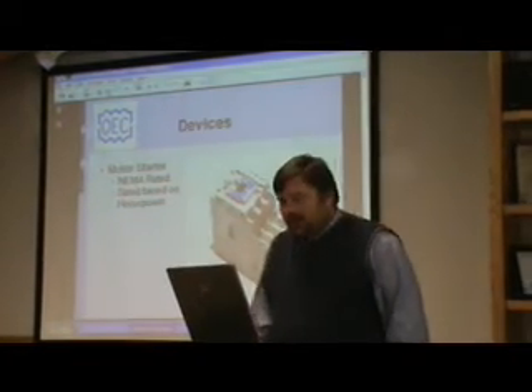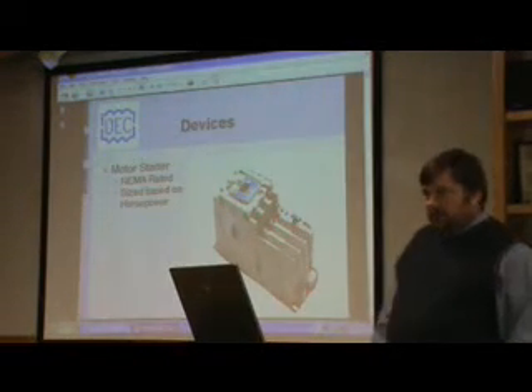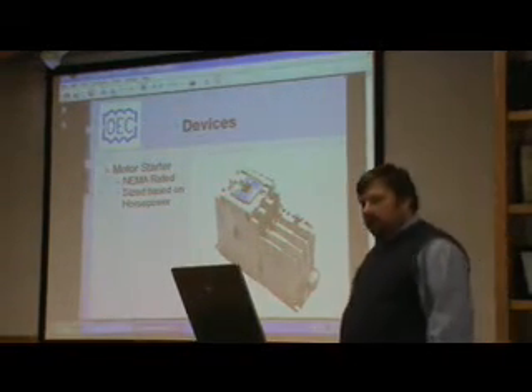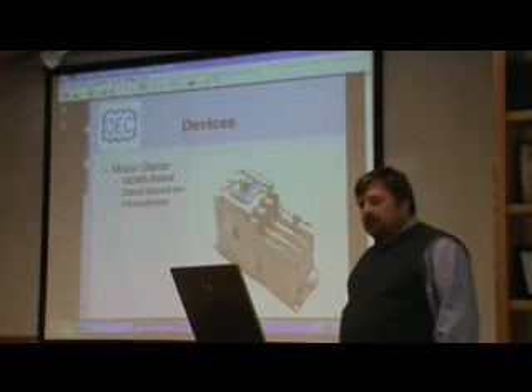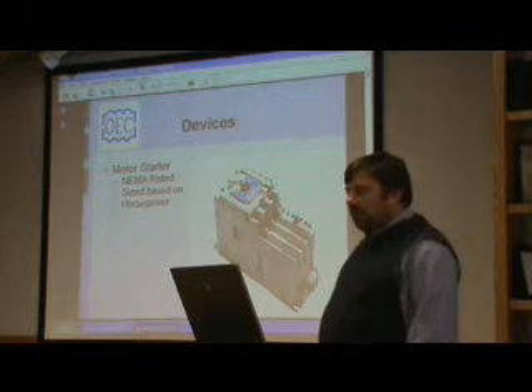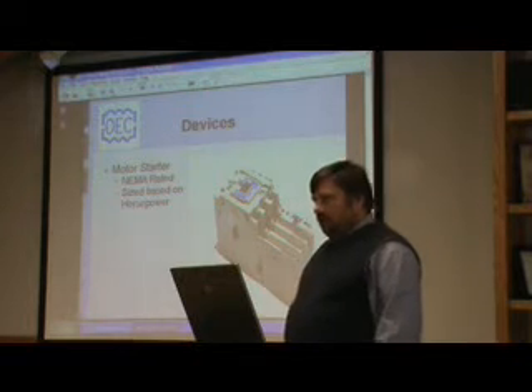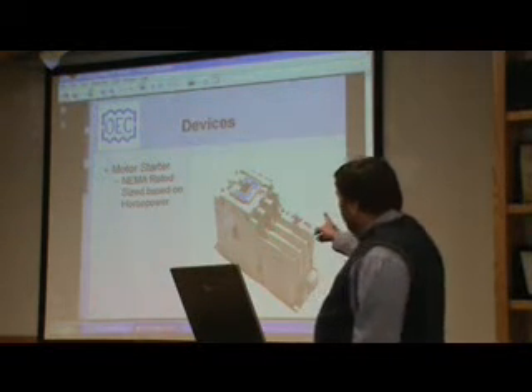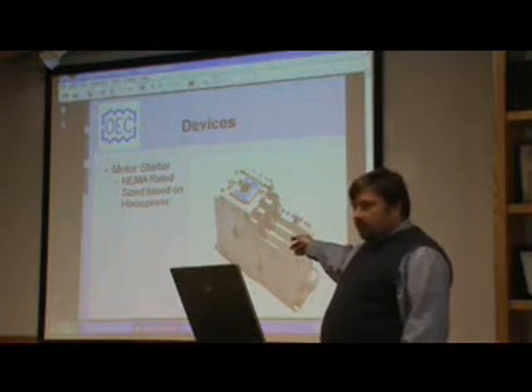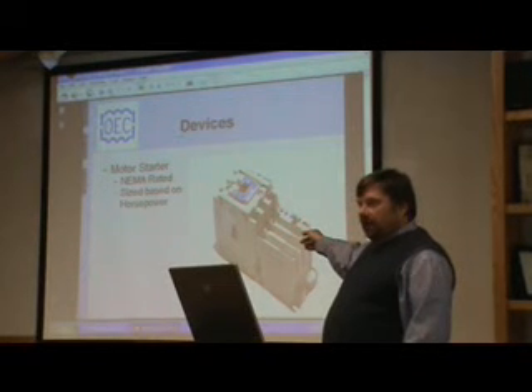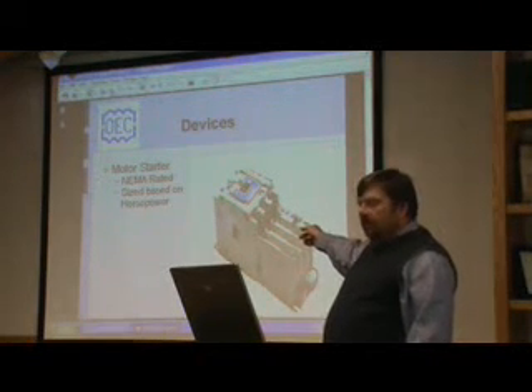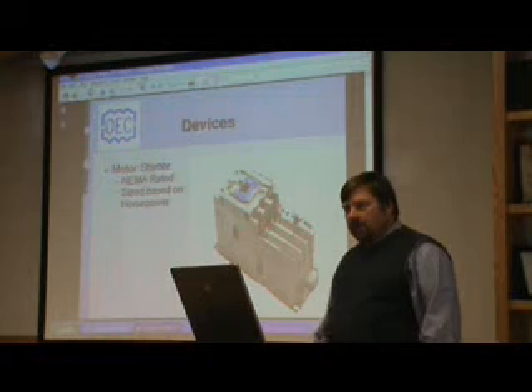This device is still selected by amperage. You want to make sure that you get the proper amperage running through it for your pump. But NEMA also has a requirement that you have to meet the horsepower rating too. So if this device is rated for 2 horsepower and you have a 3 horsepower pump that's only pulling 10 amps, and the amperage is okay, you can't use it because it has to meet the horsepower rating too.